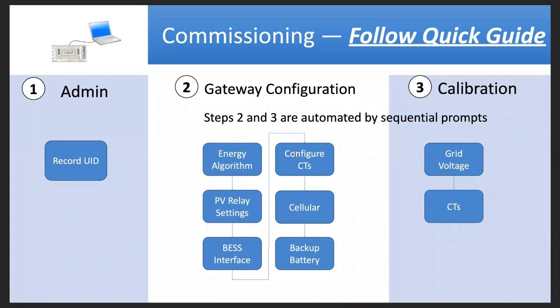Then configure the CTs. There's a guided configuration where the CTs are automatically detected. So it makes it pretty easy to identify any phase wiring issues, or if CTs are oriented the wrong way or anything like that. It's very self-guided, and it's pretty easy. I know it's kind of a lot, but that's it. I think with a little bit of attention to the online resources, and once you go through the commissioning training, you'll find that these systems are actually pretty easy to install and can be installed pretty quickly too. So that's the end of my presentation.